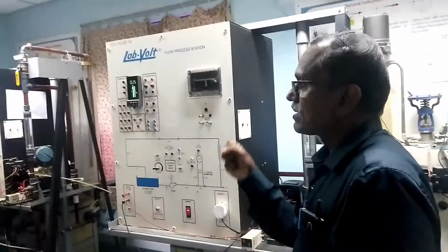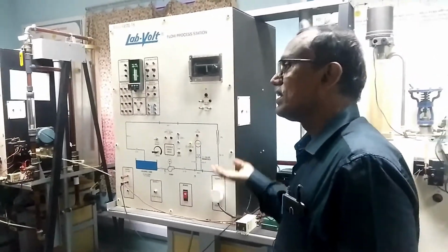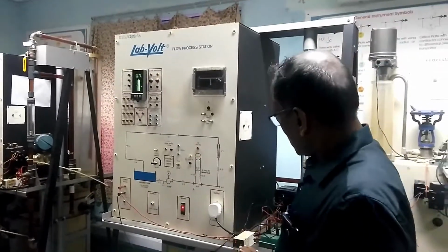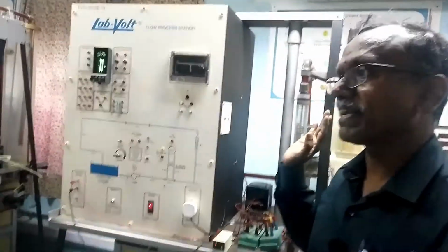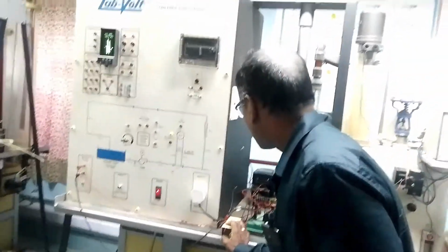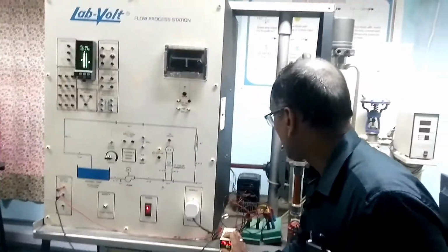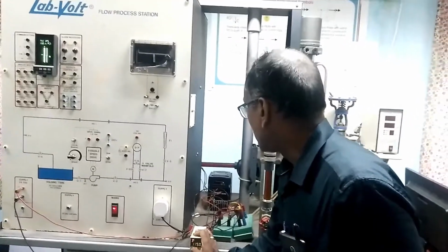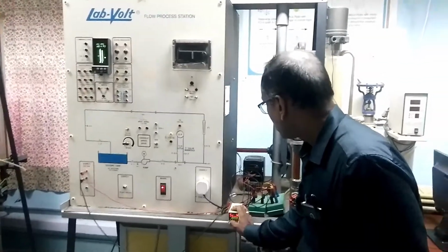But Ziegler-Nichols can still give a rough estimate. The rough estimate of PID gives oscillatory response. That's why we are increasing the PB, which means we are decreasing Kc because of the oscillation. For 115 and I equal to 6, it gives a better response. Now let us keep 115, and like that you have to write in your record. The rough estimate gives oscillatory response, so you increase the proportional band to 115 and it gives a better response. Like that you have to write.